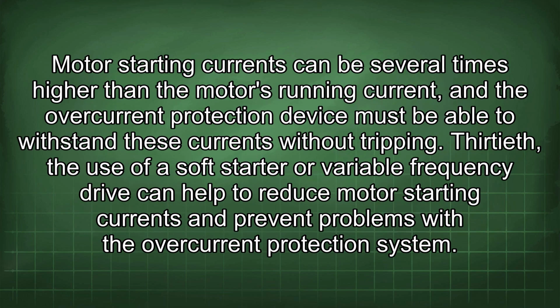Motor starting currents can be several times higher than the motor's running current, and the overcurrent protection device must be able to withstand these currents without tripping. 30th, the use of a soft starter or variable frequency drive can help to reduce motor starting currents and prevent problems with the overcurrent protection system.